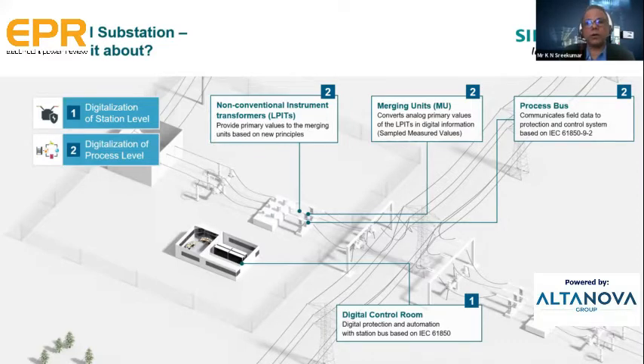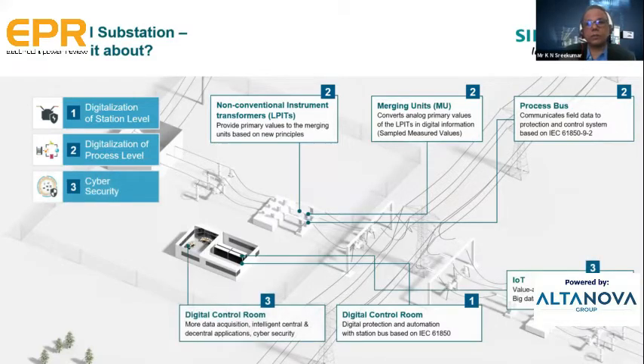LPIT meaning low power instrument transformers, which provide primary values to the merging unit, which converts the analog primary values of the LPITs into digital information, sampled measured values, and connects it to a process bus.